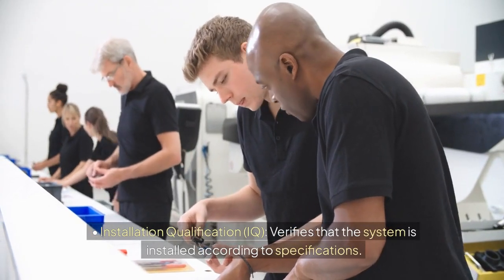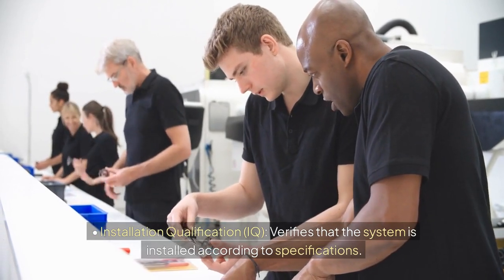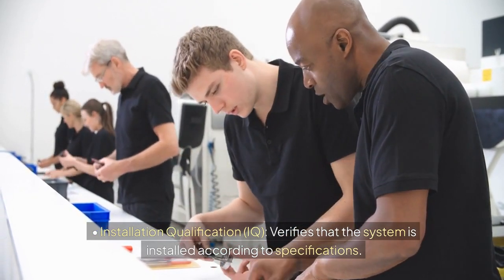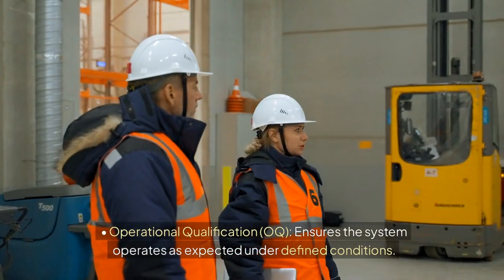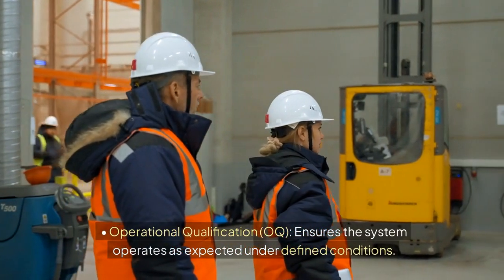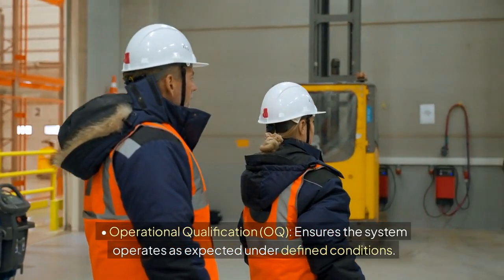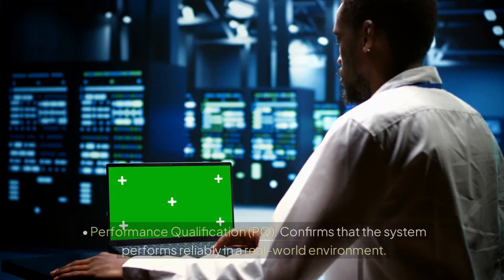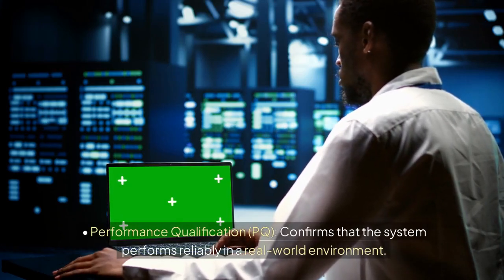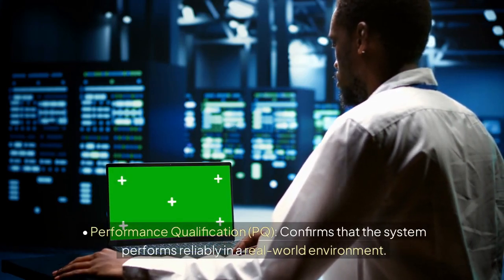Installation qualification, IQ, verifies that the system is installed according to specifications. Operational qualification, OQ, ensures the system operates as expected under defined conditions. Performance qualification, PQ, confirms that the system performs reliably in a real-world environment.